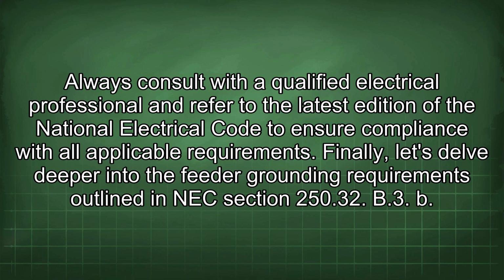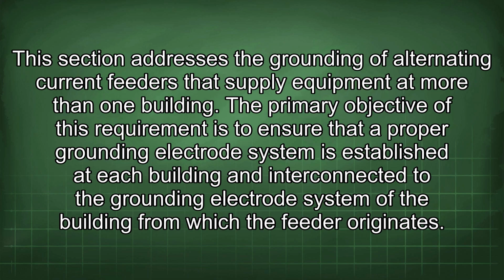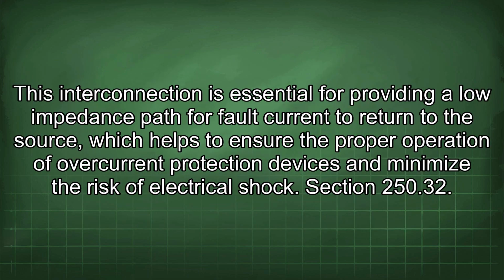Finally, let's delve deeper into the feeder grounding requirements outlined in NEC section 250.32 B3. This section addresses the grounding of alternating current feeders that supply equipment at more than one building. The primary objective of this requirement is to ensure that a proper grounding electrode system is established at each building and interconnected to the grounding electrode system of the building from which the feeder originates. This interconnection is essential for providing a low impedance path for fault current to return to the source, which helps to ensure the proper operation of overcurrent protection devices and minimize the risk of electrical shock.